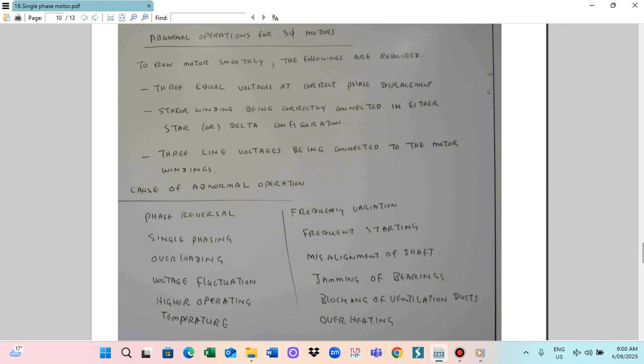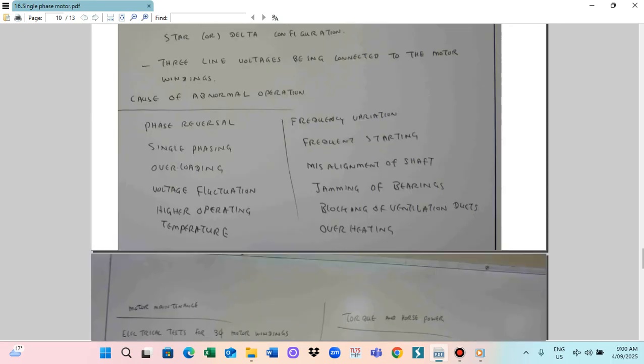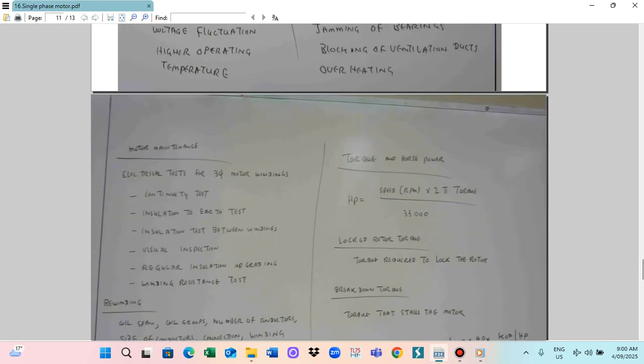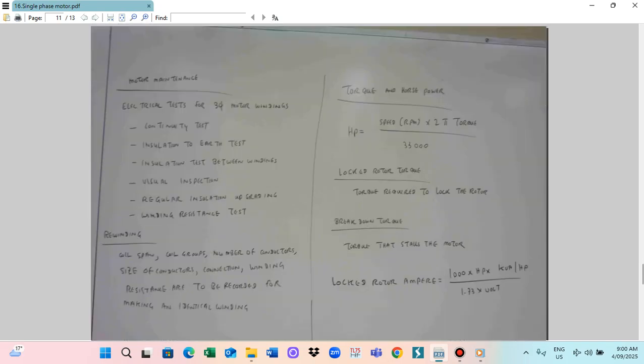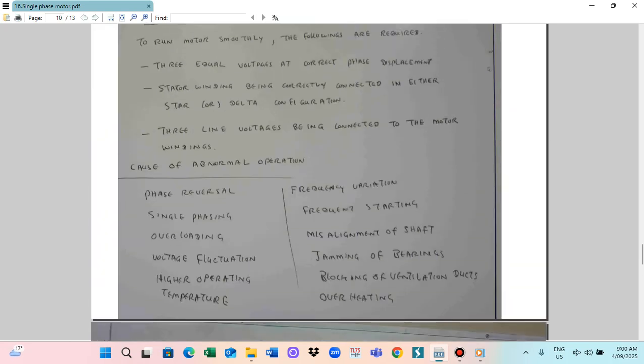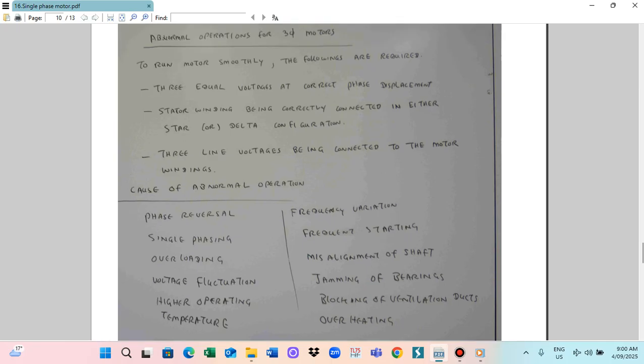Sometimes there is the clearance when you fix the motor. This is the motor here, this is the armature, and this was the end plate. The end plate and the motor's rotor should have clearance. Sometimes when you fix it, the end plate is not clear of the motor's rotor, so the rotor will be overloaded. The motor then draws a higher current, so the circuit breaker trips off. This is the way that it happens.